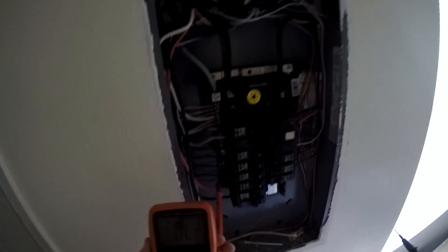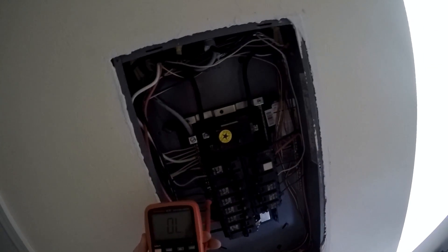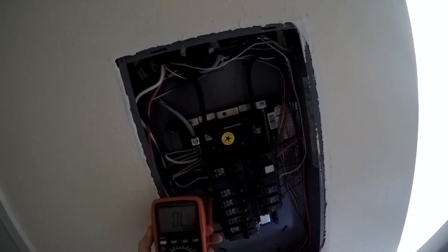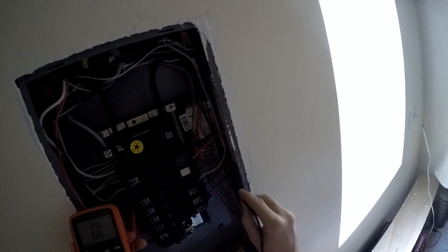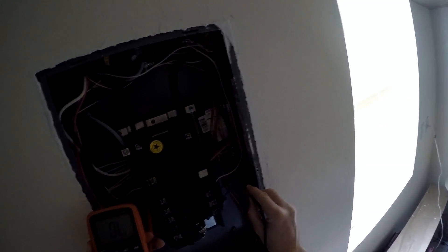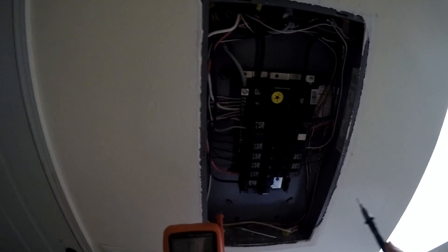Got power to this panel now, but I've got everything shut off. The main breaker is shut off, but there is 240 volts sitting right there, so I gotta be careful poking around here. I did want to show that the common here and the ground are connected. They're not connected here, but they're connected back in the main panel of the house.